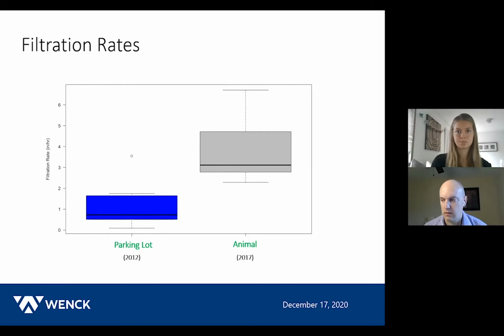My thought there is that as water runs into that sand layer, it's just acting like a sponge. That water is getting into that sand layer, and that is actually acting as the storage for runoff. And the drain tile below it, there's some rate reduction there, but that sand is still not consolidated enough, or there's enough void space in there that the water never increased into the pipe storage, which is where our pressure transducer was located.